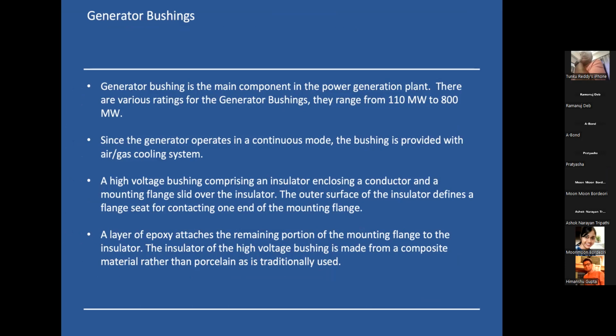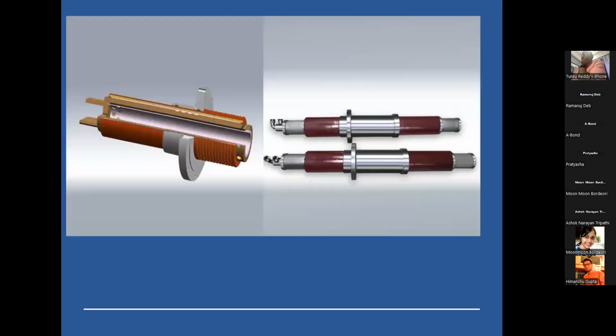Now, a high voltage bushing comprises an insulator. It also comprises a conductor and a mounting flange over the insulator. The insulator in our case is a composite material rather than porcelain. In our case, we use epoxy resin. So this is very crucial. This is a small picture of our generator bushing. It's a 3D CAD file.